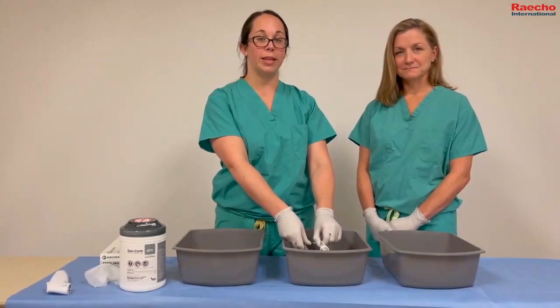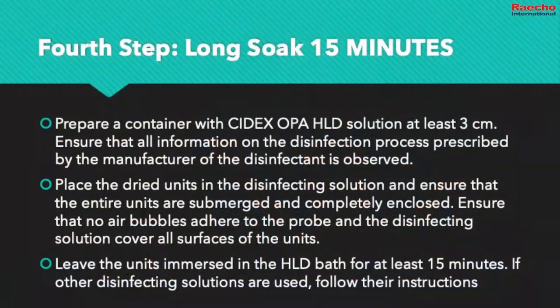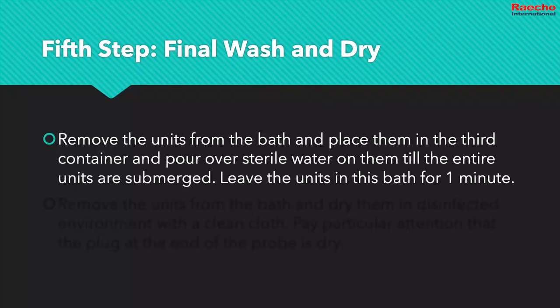Leave the units immersed in the high-level disinfectant bath for at least 15 minutes. If other disinfecting solutions are used, follow the instructions of the manufacturers. The fifth step is a final wash and dry. Remove the probes from the disinfectant bath and place them in a third container.